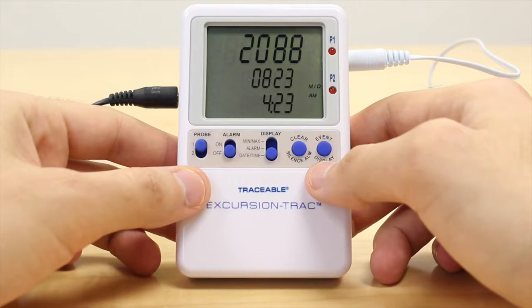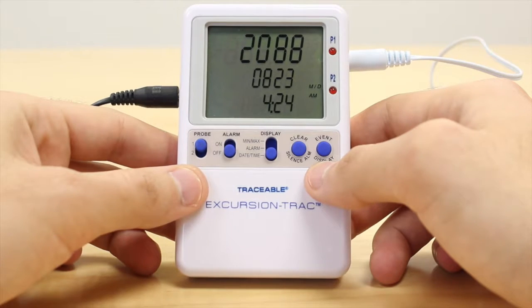Not only that, but your excursion track thermometer also has the capabilities to show you the last time either probe went out of your set range and back inside your set range. Last but not least, your excursion track is also capable of storing the last 10 alarm events that occurred, and you can review them by downloading your data to the computer. This feature will be explained in greater detail in the Reviewing Stored Data video. For now, let's begin setting the alarm limits.